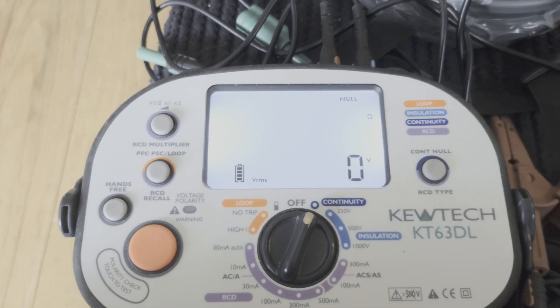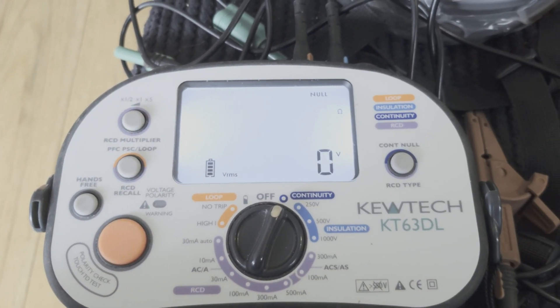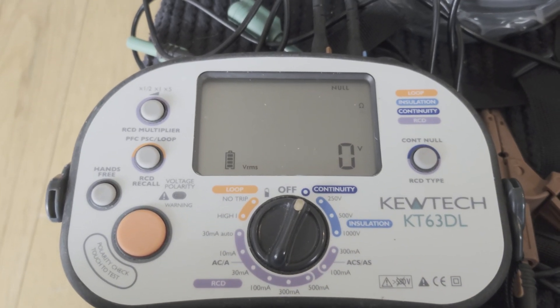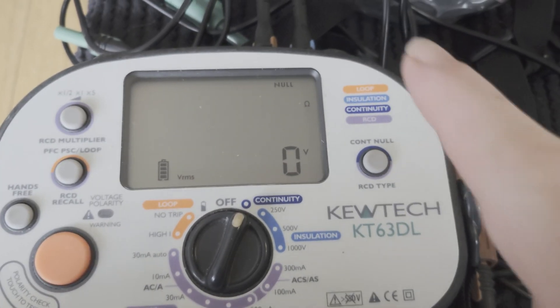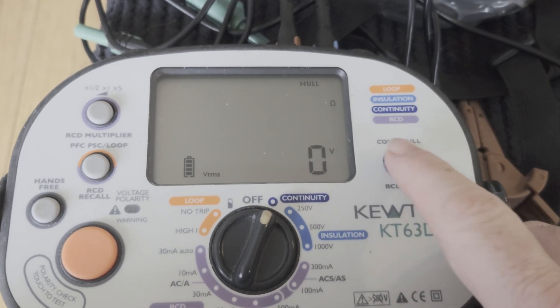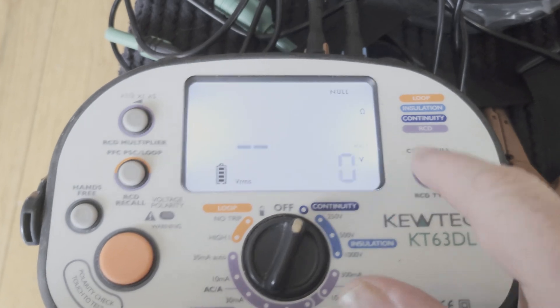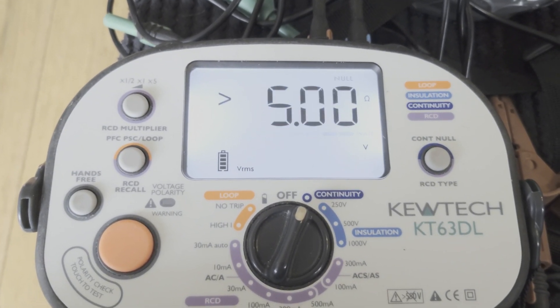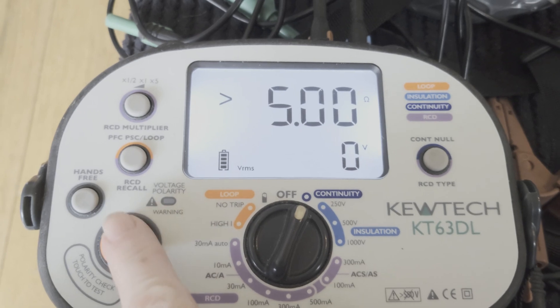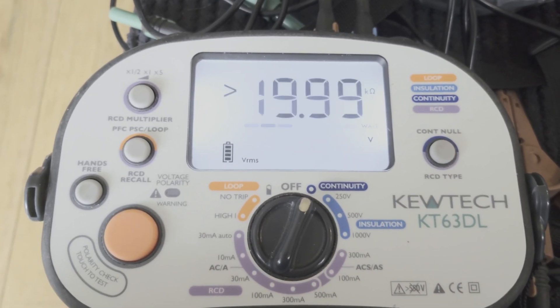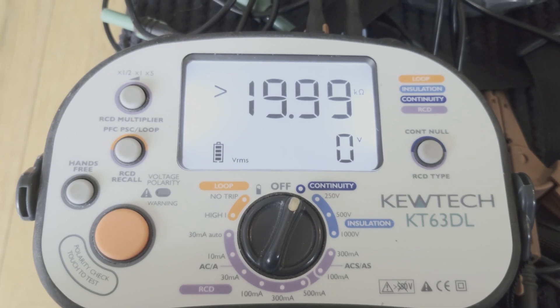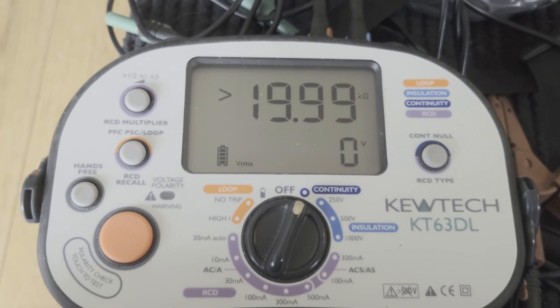So to do the nulling, turn it to continuity. Now as you can see at the top I've already got the null in there. I could use these straight on the cable and it would work, but for this test what we're going to do is I'm going to clear that. So to clear it, the crocodile clips are disconnected, press the null button. You'll get that. And I do this, I don't think you have to, but I do anyway just to make sure that it's completely cleared for the nulling, so we can now null these leads.